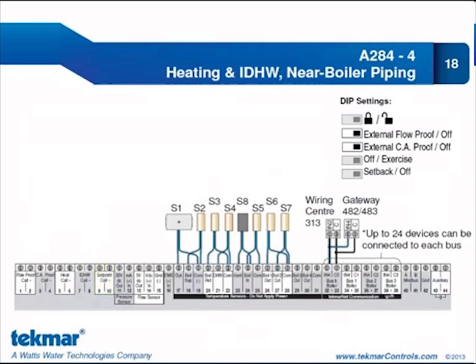Looking at our sensors, we have an outdoor sensor to provide outdoor temperature reset to the space heating zones. We also have our boiler supply, boiler return, domestic hot water sensor. S8 is our vent sensor, which we talked about on the previous slide, and that will allow us to monitor vent temperatures, and if we choose to, we can even limit vent temperatures in order to protect that non-metallic vent material that we often see in place when we have condensing type boilers. The remaining sensors are the boiler inlet sensor and the boiler outlet sensors for each of our two boilers.